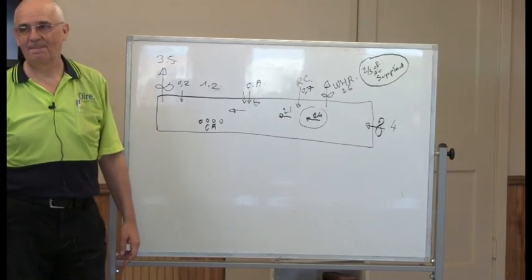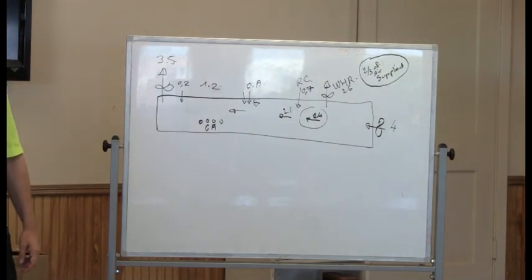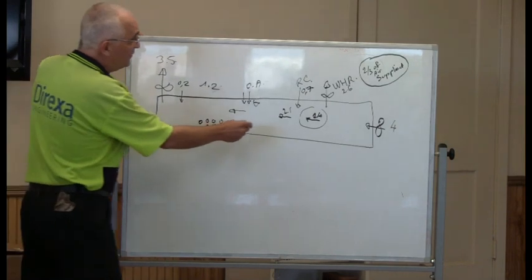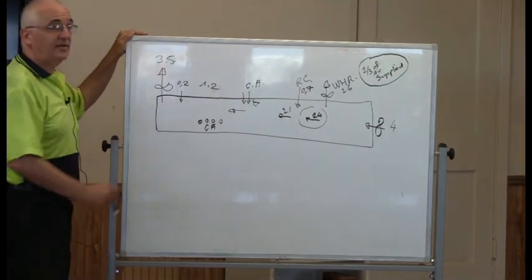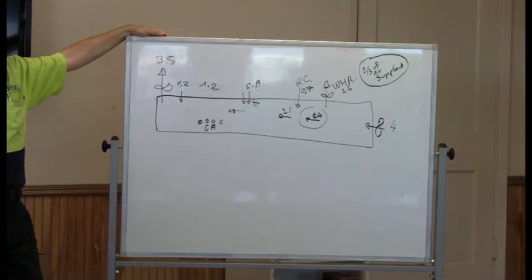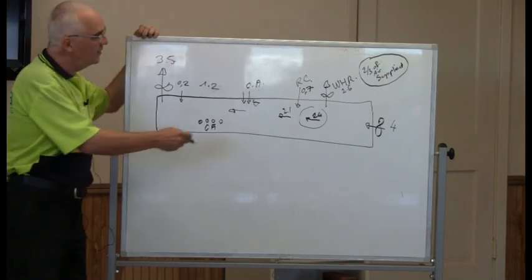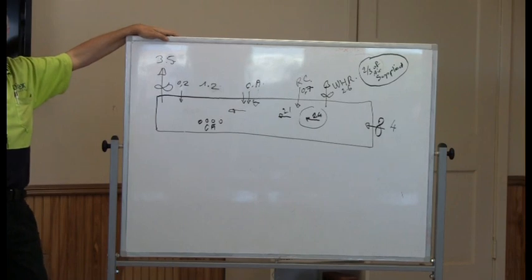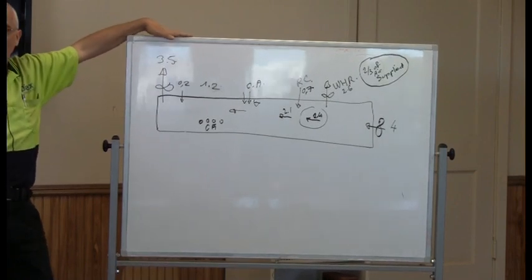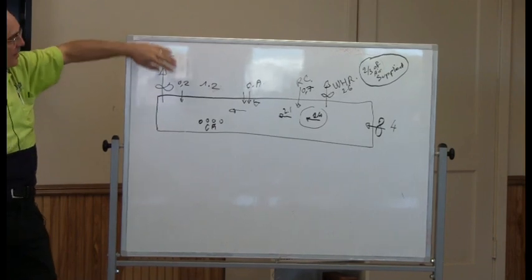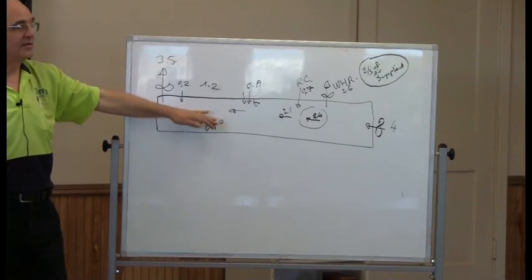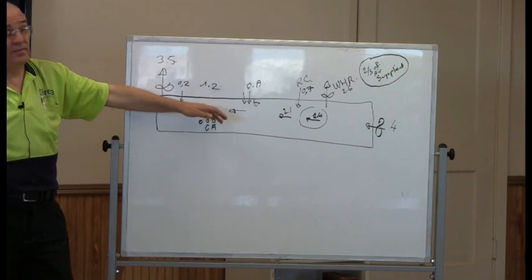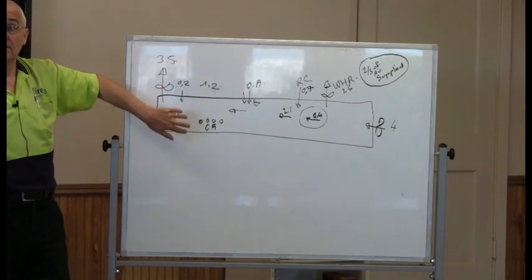Right. That air is what temperature? That air, that 2.1 moving down the tunnel, is what temperature? It's energy. It's energy that you supply, because, you know, I talked about the heat distribution, but the side burner here should not be working like crazy to maintain temperature, or something is really wrong in the sizing. You should have plenty of energy coming through, that those burners are here to supply a complement of energy, but not work. When people have to double their quantity of burners to keep up the temperature here, a lot of time it's because the energy which was available here is not coming. So you have to cheat.